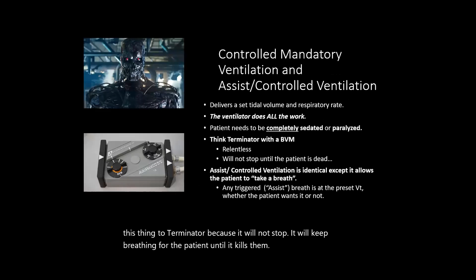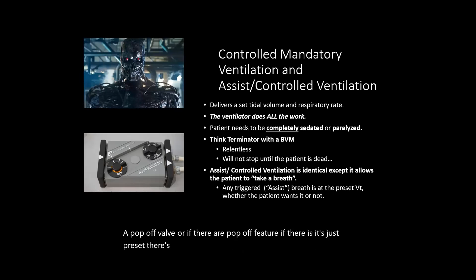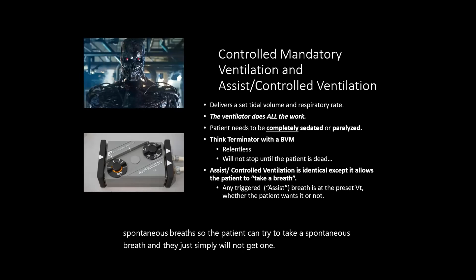But you can see there's basically two functions on here. There's respiratory rate and tidal volume. Not necessarily a pop-off valve, or if there is a pop-off feature, it's just preset. There's no ability for it to assist or compensate for spontaneous breaths. So the patient can try to take a spontaneous breath and they just simply will not get one, no matter how hard they try. This type of ventilator is best for patients who are completely paralyzed, who have no respiratory function, who are completely apneic, and who are very, very sedated.